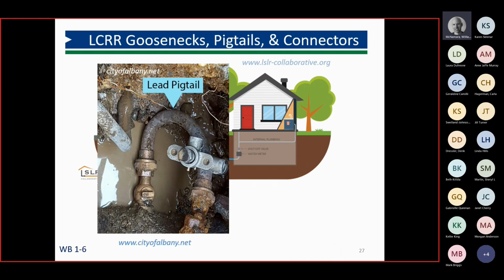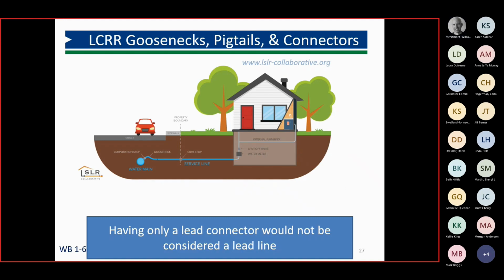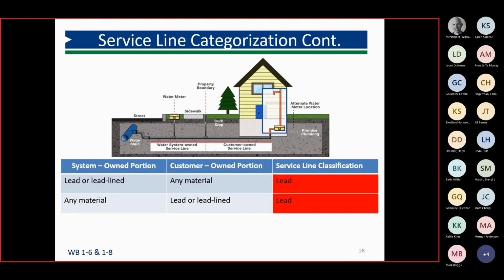Another popular one is a lead pigtail. I'm bringing these up because if they only have a lead connector, and let's say it's connected to copper, that is not going to make it a lead service line. Now it does affect galvanized, we'll talk about that in a little bit, but only having a lead connector is not going to make it a lead service line.